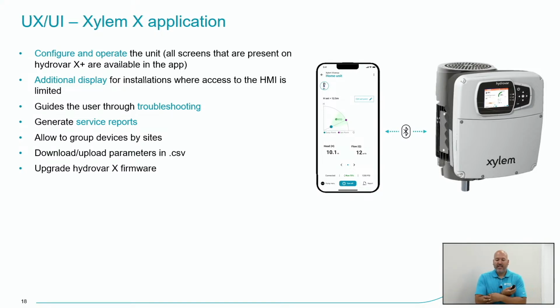So the Xylem X app, that is the name of the application if you want to go ahead and download it. It's Xylem X. That's going to be the Hydrovar X mobile application. As I mentioned, it's basically an additional display. So if this is in a restricted space, so you just don't necessarily want to bend down to program the unit that may be on the floor or something of that nature, you can connect to the Hydrovar X via Bluetooth, use the mobile application, and you'll be able to configure and even operate the unit from there.